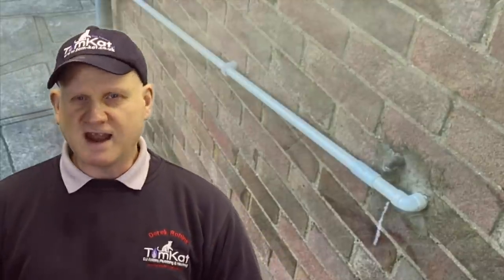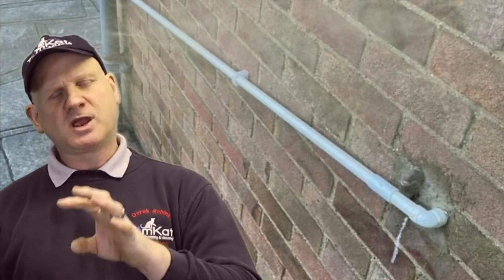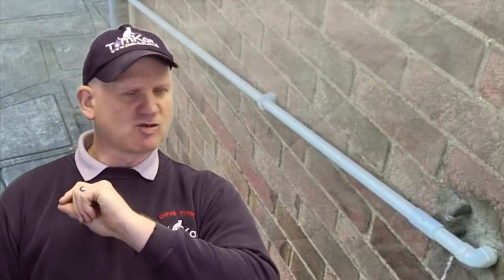So even when an engineer goes out to service or repair a boiler, they should be looking at the way the condensing pipe has been run. And if it is run outside and it's done in just overflow pipe, or it's done in 32 waste pipe and it's not insulated, then the engineer has the responsibility to inform the responsible person that the condensate pipe is not to current regulations and should be upgraded. You don't need to pin them down on the floor and tell them that you've got to have it done. No, you've just got to kind of inform them it must be done.